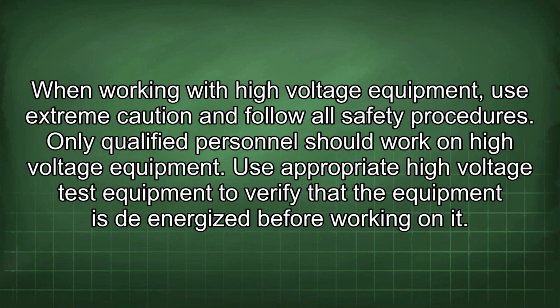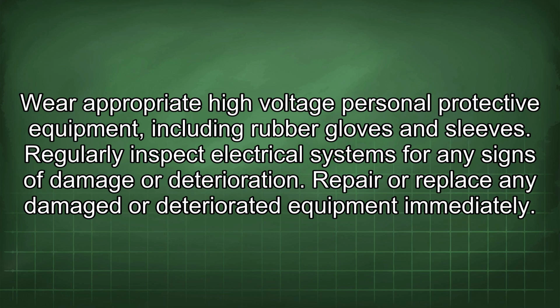When working with high voltage equipment, use extreme caution and follow all safety procedures. Only qualified personnel should work on high voltage equipment. Use appropriate high voltage test equipment to verify that the equipment is de-energized before working on it. Wear appropriate high voltage personal protective equipment, including rubber gloves and sleeves.